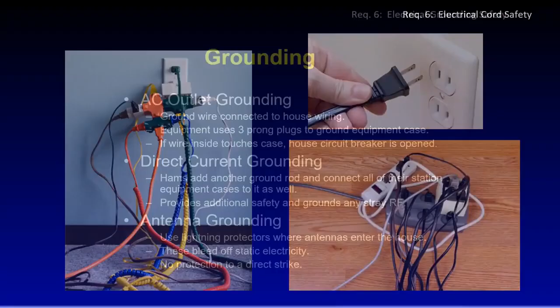In your house you have a little AC outlet plug, and there are two types of wires: a neutral, and a grounding circuit. The grounding circuit is hooked into the box and has a copper wire that goes outside the house and is driven down into the ground about 8 feet. That's the grounding part. So if it's hooked up right, if there's any short, the current's going to go back into that wiring system and down to the ground.